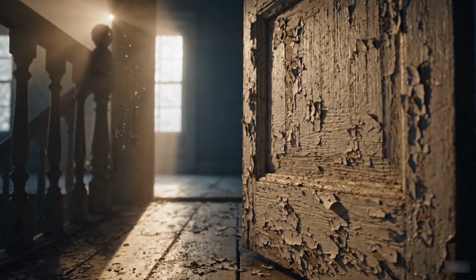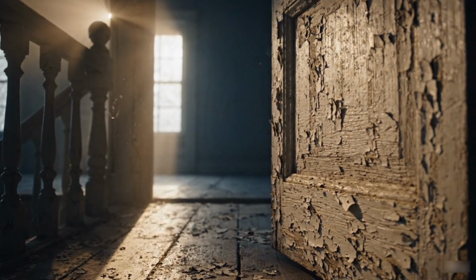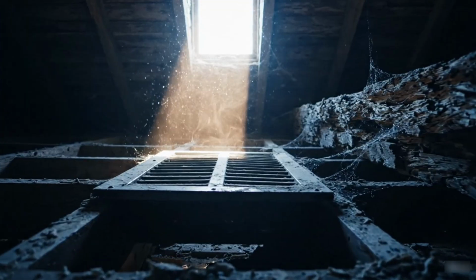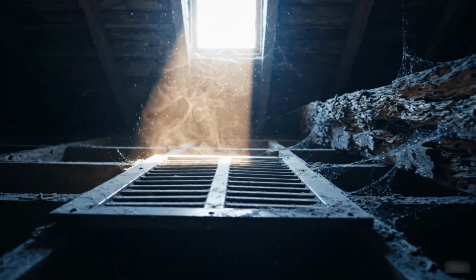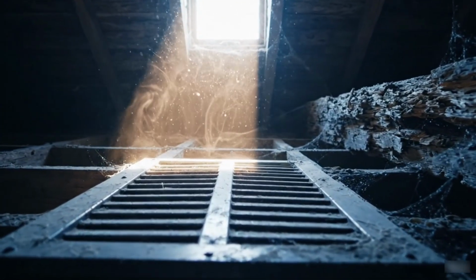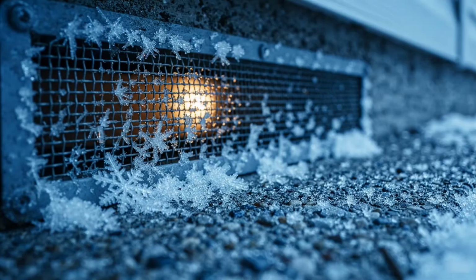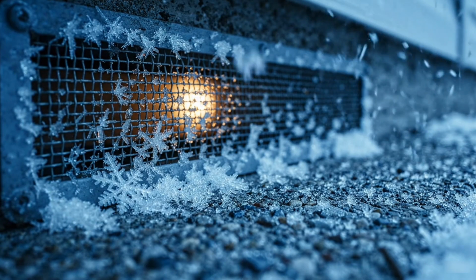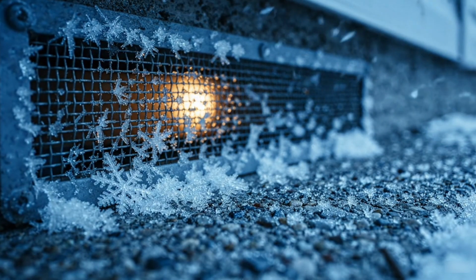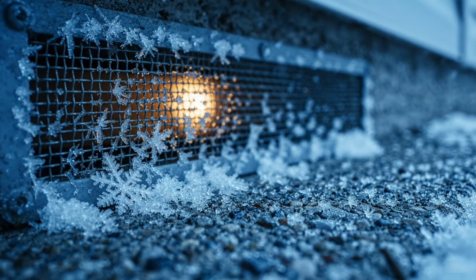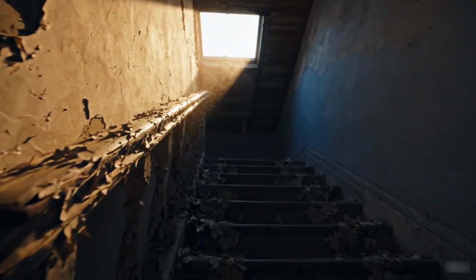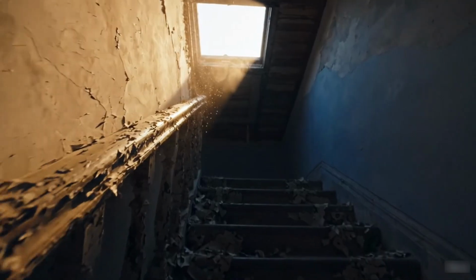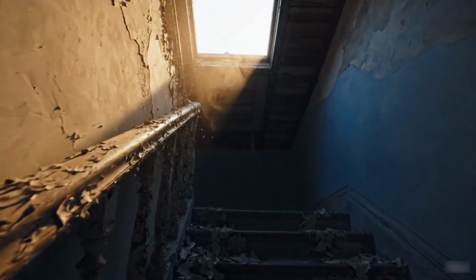Step 7. Test the system. On a sunny day when the outdoor temperature is above 80 degrees, go into your attic at 2 in the afternoon. Hold a lit incense stick or a piece of smoke from a blown-out match near the gable vent opening. You should see the smoke drawn toward the vent and pulled outside. If the smoke hangs still or drifts downward, your intake path is blocked. Check that the foundation vents and ground floor window are open.